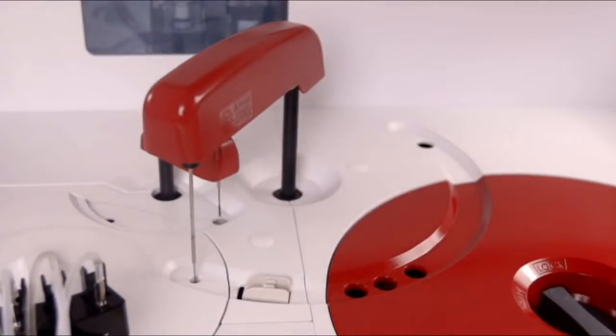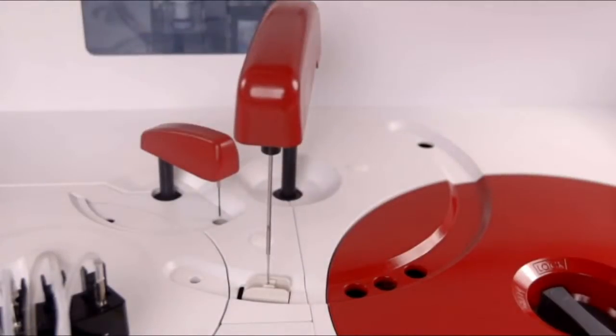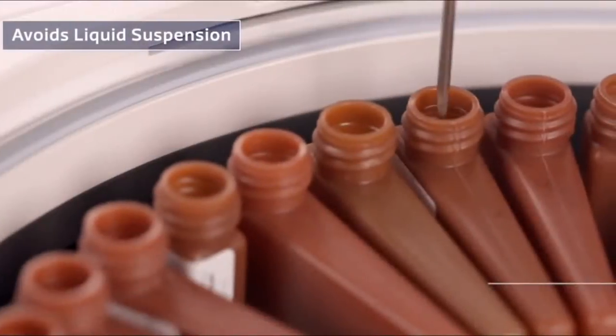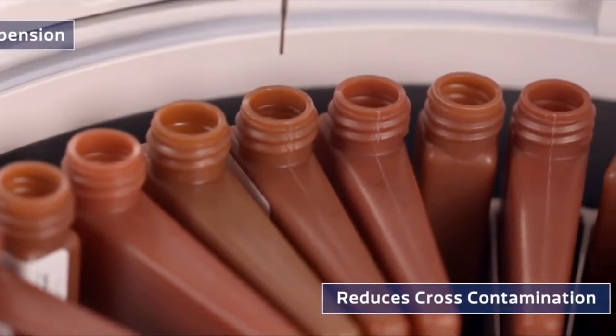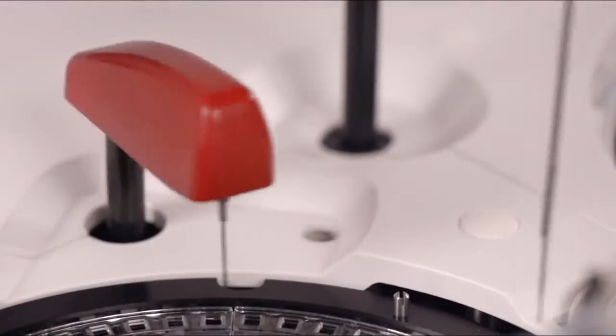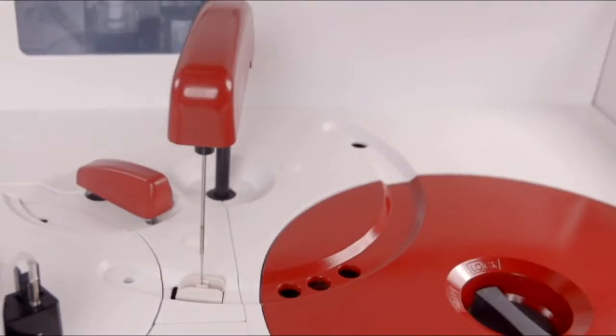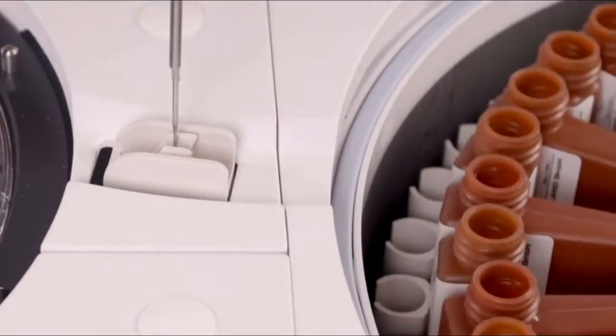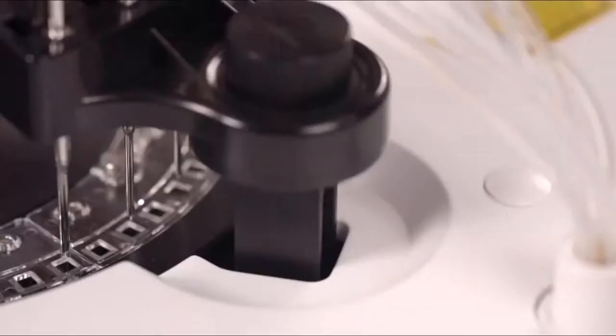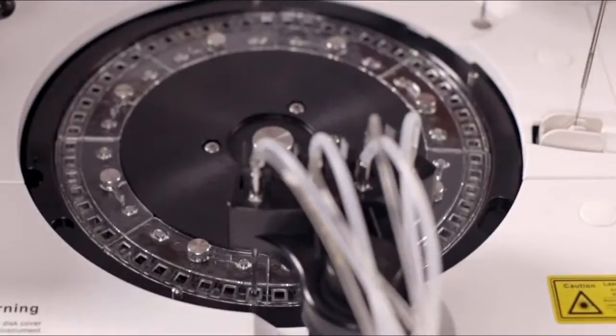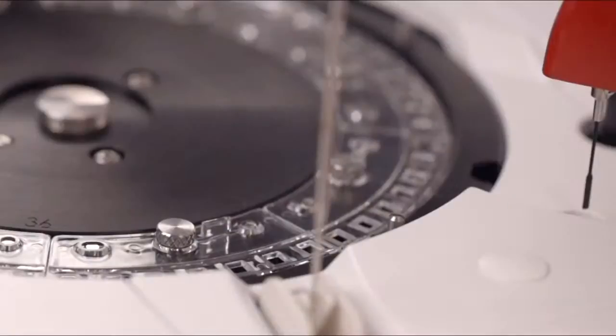MISPA CXL Pro contains a Teflon-coated stirrer mixer, which avoids liquid suspension and reduces cross-contamination. Triple-speed mixing mechanism is highly efficient for latex-based assays. With 56 rigid semi-permanent cuvettes, MISPA CXL Pro is able to perform more tests per batch compared to other equipment in the segment.